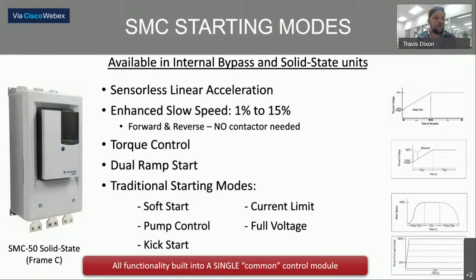You can run it from 1 to 15% of the full motor speed in 1% increments, and you can do that both forward and reverse without a reversing contactor. So for example, if you have a 1800 RPM motor, that slow speed operation can be plus or minus, down to 270 RPMs. Torque control is also new. Also included are all the traditional start modes with the SMC Flex and SMC 50.